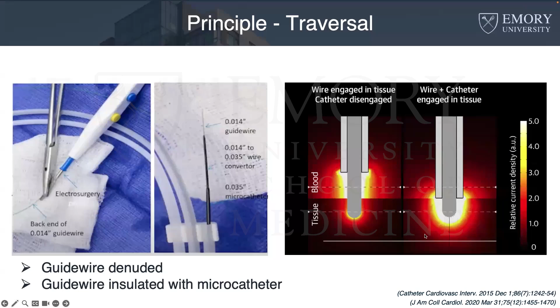Now, when lacerating the tissue, the back end of the guide wire is configured in the same way and attached to the electrosurgical pencil. But for laceration, instead of delivering radiofrequency to the tip of the guide wire, it delivers radiofrequency to the mid shaft of the guide wire. And how it does that is the guide wire is kinked at the mid shaft, and the inner curve is focally denuded by scalpel. And this becomes the active electrode and the cutting edge surface, where the radiofrequency is focally concentrated, and we call this configuration the flying V.